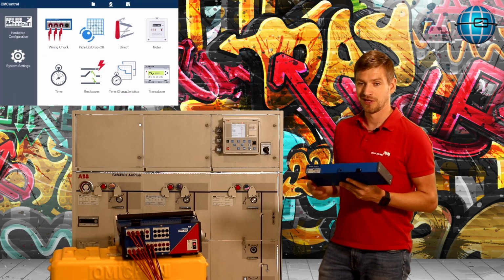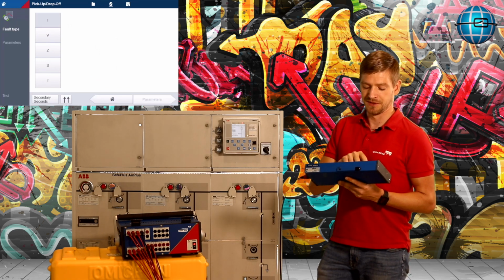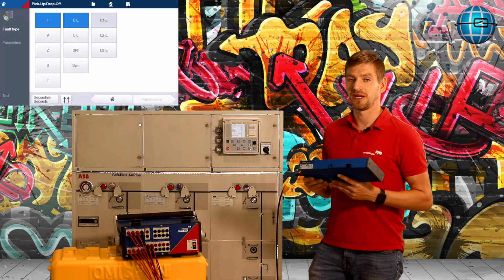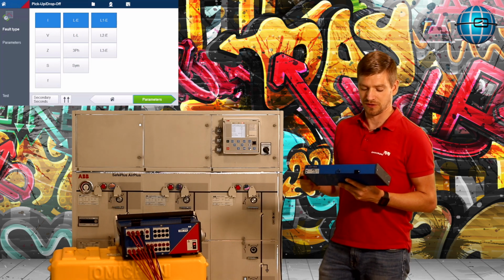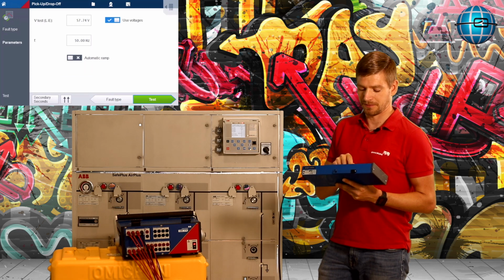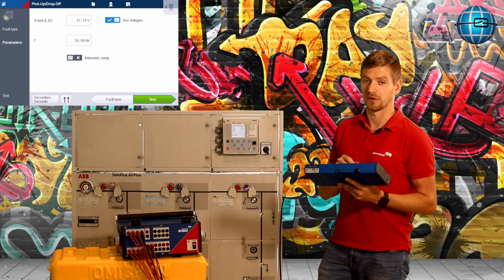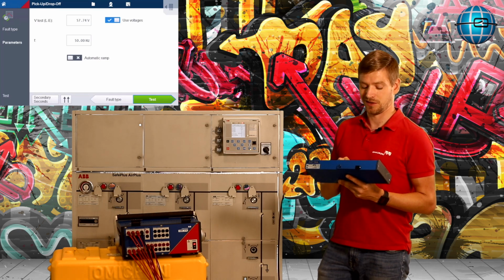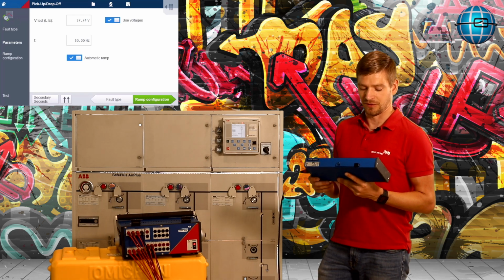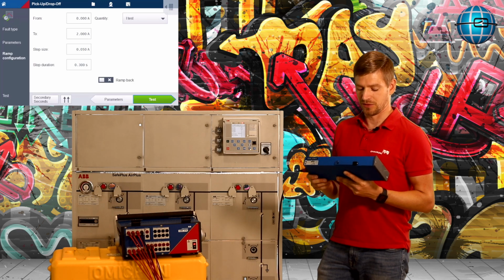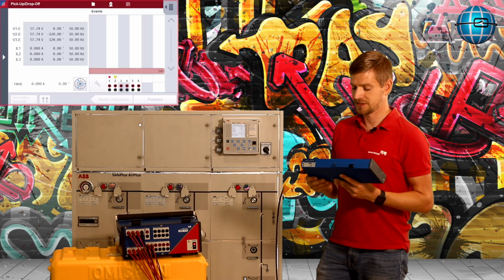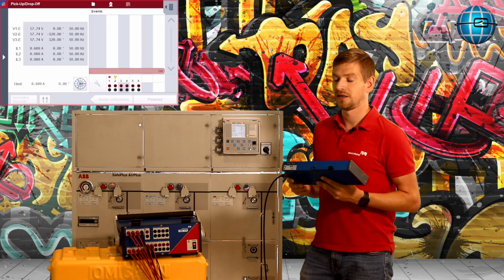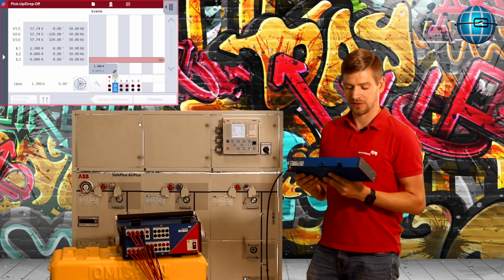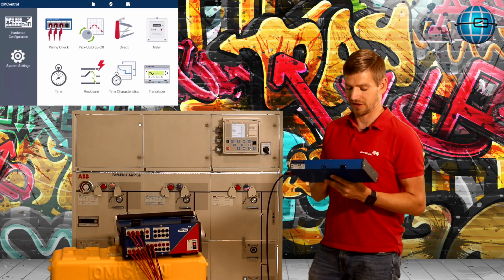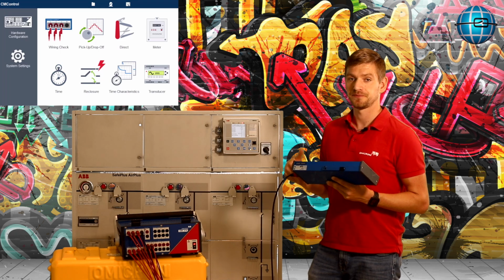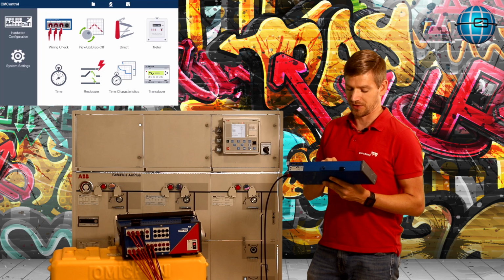Therefore, we have here this ramping tool in CM control, and here I will start with the currents. So we have a pickup value of 1.3 amp configured here, and here you can choose your ramp type. You can enter some parameters, for example, if you would like to have also voltages in parallel for directional overcurrent protection, and you can use this automatic ramp. Very useful, then you're very quick in the test. So now going to the test screen, starting the injection, and CM control will automatically ramp up the current, and at 1.3 amp the relay will trip. Okay, perfect. So we verified that there is no additional protection working below 1.3 amp.